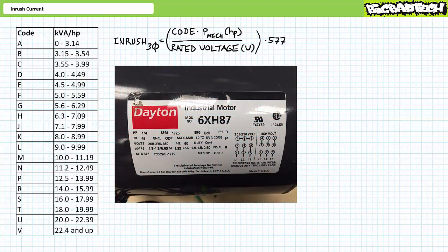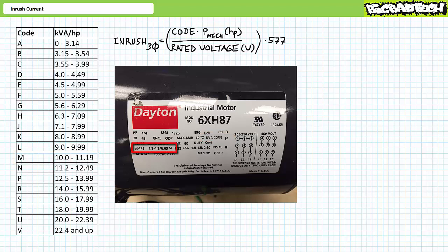Consider a quarter-horsepower motor intended to operate using 208-volt three-phase AC in the low-voltage configuration with a locked rotor code of M, meaning it has a kilovolt ampere per horsepower constant with a low of 10 up to a high of 11.19. Center of mass would be the average of these two numbers at 10.6. The rated current of this motor operated at 208 volts is 1.3 amps. If we wanted a quick rough estimate of inrush, we could say we might expect a momentary surge of six times 1.3 amps, or roughly 7.8 amps.